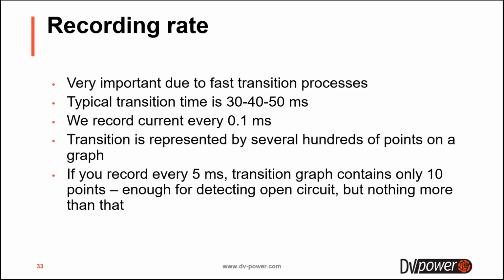And that gives a very good resolution to analyze the graph, to see all those processes, all those characteristic points and characteristic parts on the graph. For example, if you would do it with a lower recording rate, let's say 5 milliseconds, then your typical transition graph would contain only 10 points, if it's a 50 milliseconds transition. And that is enough just to detect whether there is an open circuit during the transition. But you will not be able to do anything more than that. The resolution will simply not be good enough to detect the characteristic points and the timings of those characteristic parts of the graph.